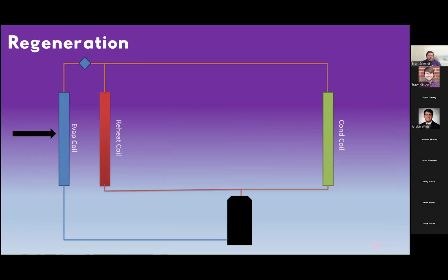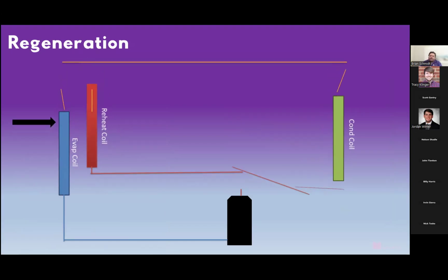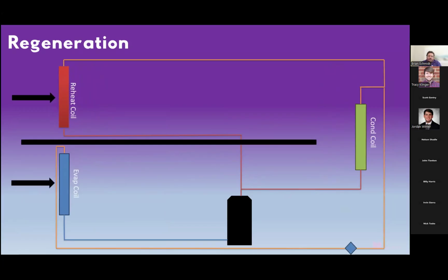So we don't have what you would consider necessarily a hot gas reheat coil. I made a little diagram here to show what you traditionally have with the reheat coil. You have your evaporator coil, the air comes in, cools down, gets below the dew point, you reheat to a space neutral condition, and you supply it to the space. What we've done is we've moved that reheat coil. Instead of being behind the evaporator coil, it is now in its own air tunnel. Same idea in terms of how the hot gas is flowing, but we now have it in its own air tunnel. That is the regeneration air tunnel.